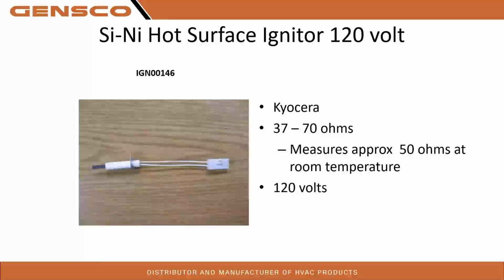Okay, so here's our hot surface igniter for 120 volt. This is silicon nitride. It's built by Kyocera, 37 to 70 ohms. It's going to measure about 50 ohms at room temperature. It's going to be a 120 volt unit. You can see in this picture that the ceramic is not round. So like I said, it doesn't always play across that way, but it is a decent rule of thumb.